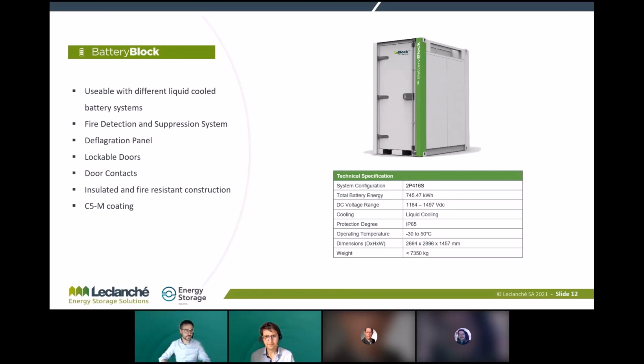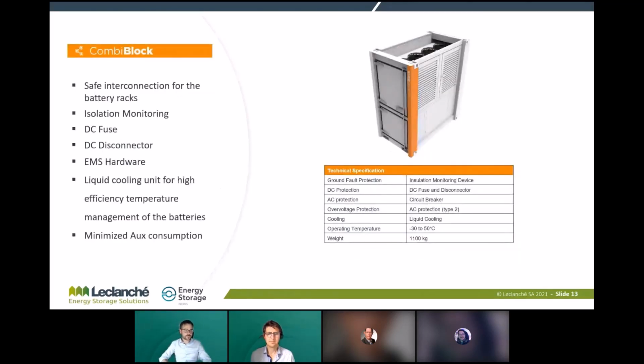The entire enclosure is C5M coated. The combi block is divided into two sections: on top, the cooling equipment with the chiller and compressor, and on the bottom, the necessary infrastructure for a battery system, like fuses, disconnectors, energy management hardware, isolation monitoring, and additional equipment needed for project installation.